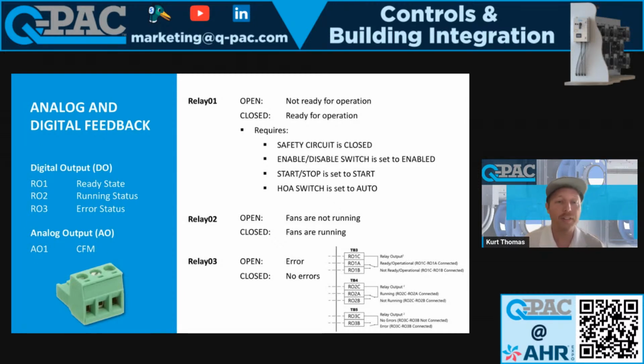So if you get 5 volts, then it's going to be half of the CFM between 0 and that high value that we give you in the HMI. No difficult calculations there, just interpolating. Then we have some digital outputs.